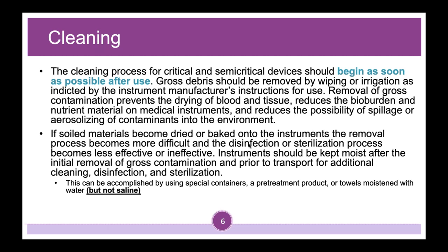They should immediately be getting sprayed down with an enzymatic cleaner. They should be getting cleaned throughout the procedure to make sure bioburden is not adhering to it, caking on it, and drying. Gross debris should be removed by wiping or irrigation as indicated by the instrument manufacturer's instructions for use. Removal of gross contamination prevents the drying of blood and tissue, reduces the bioburden and nutrient material on medical instruments, and reduces the possibility of spillage or aerosolizing of contaminants into the environment.